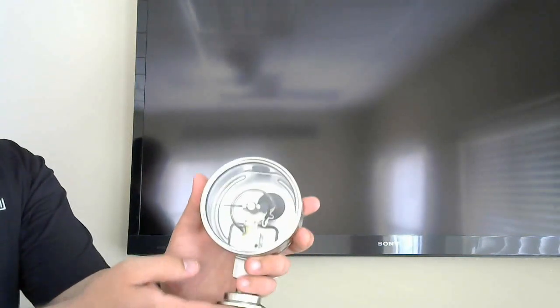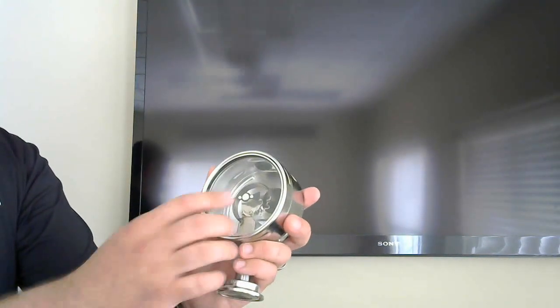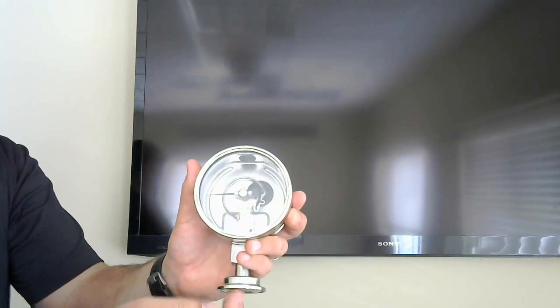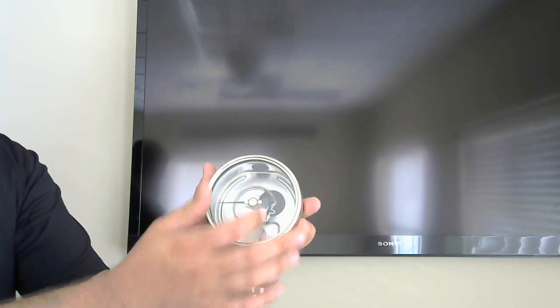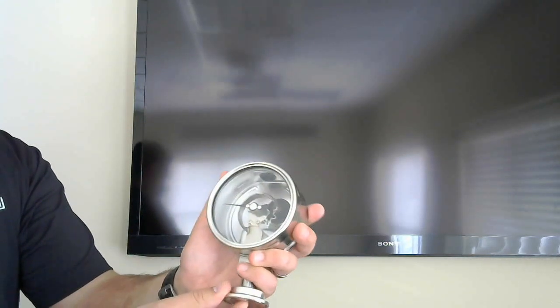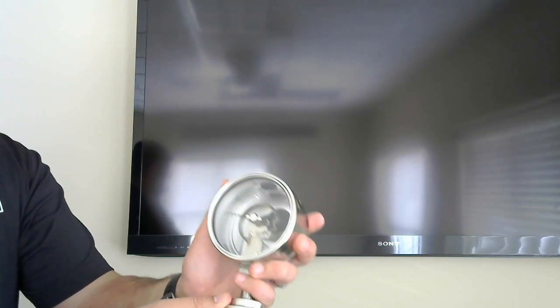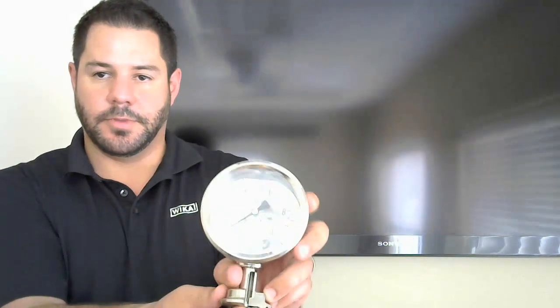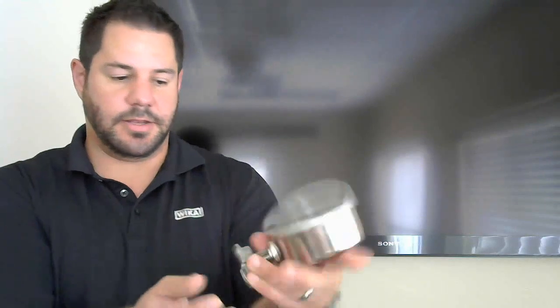One thing I didn't mention about our standard gauges is that when you have a diaphragm failure and lose that fill fluid, the gauge keeps working because your process goes back into the bourdon tube. So your gauge still has fluid in it making it work, and there's no indication that the gauge has ever quit working. That's a benefit that makes this better: the second the diaphragm fails, this gauge starts reading 0.